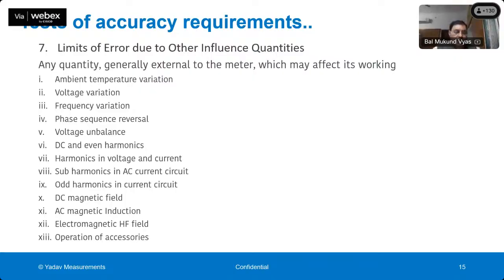Another very important one is DC magnetic field and AC magnetic field. These tests have two types of reasons behind why they are conducted. Because when the meter is installed, there is electrical wiring around it, and there will always be some magnetic field present, and it can be DC and it can be AC magnetic field also. So this magnetic field should not affect the accuracy of the meter.